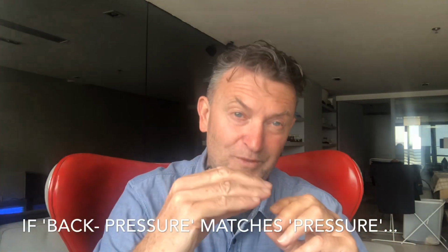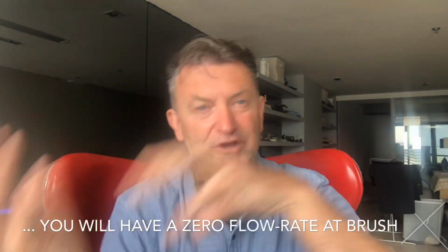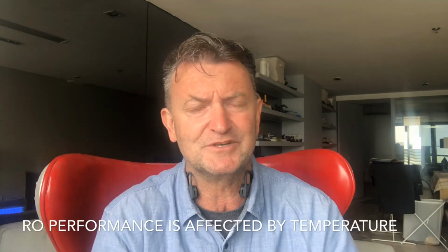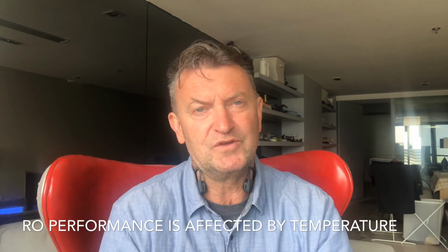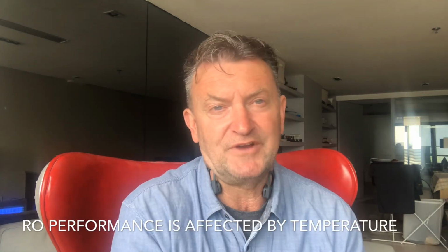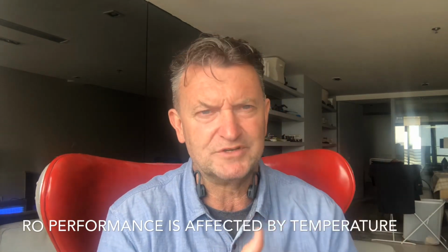So the more back pressure you've got, the less flow rate you're going to get out of your reverse osmosis membrane. And also we've got the problem with water temperature, is that the performance of a reverse osmosis membrane when the water temperature is 75 degrees Fahrenheit or 25 degrees Celsius is double that of when the water is at 39 degrees Fahrenheit or about 4 or 5 degrees Celsius. Okay, so with water temperature, the spring is difficult to get the best performance out of an RO because the ground is freezing. Even if the ambient temperature is lovely, it's the groundwater temperature that's driving the temperature of the water that's coming into your RO.